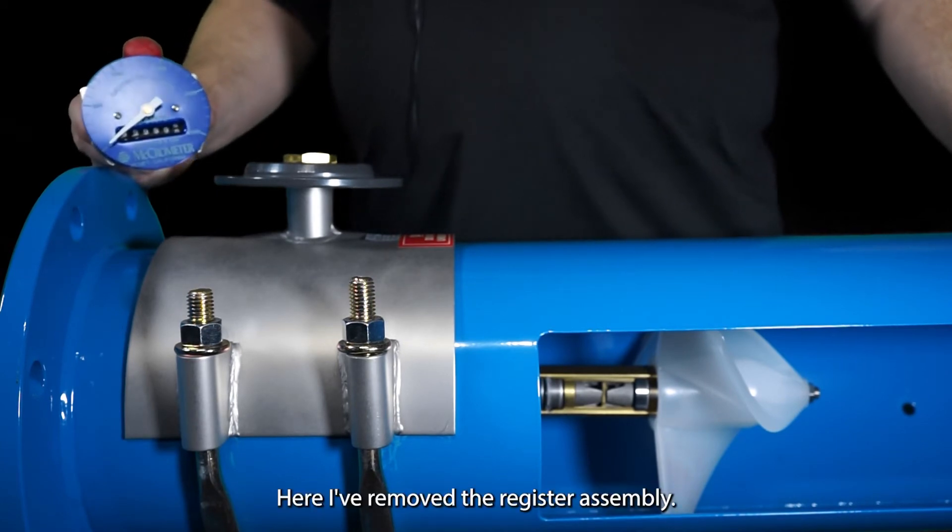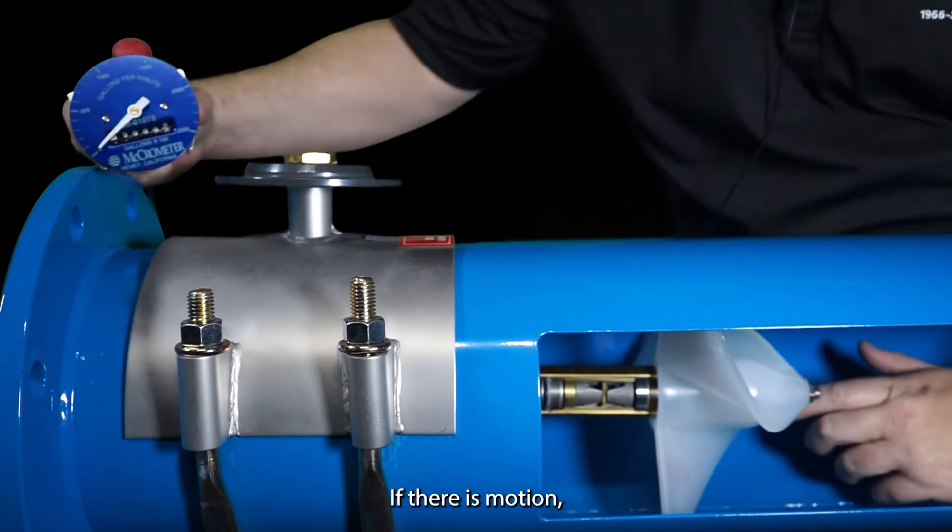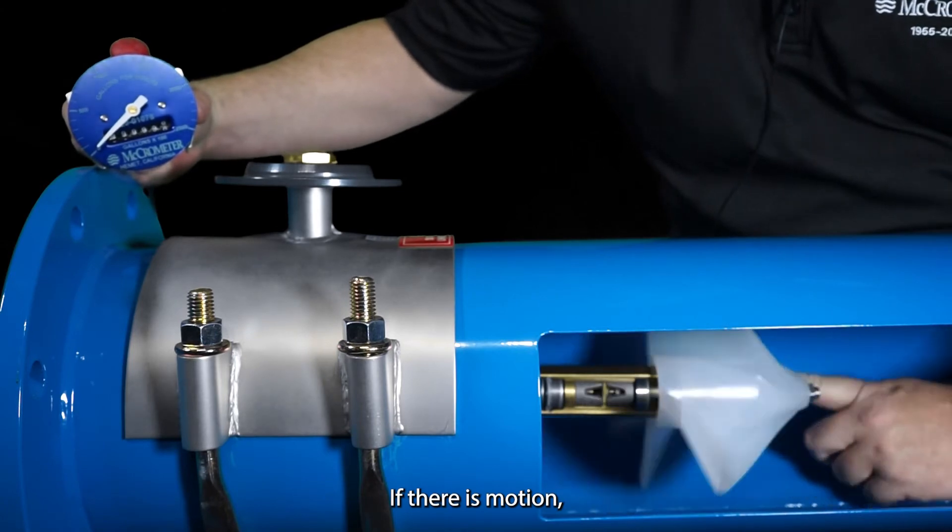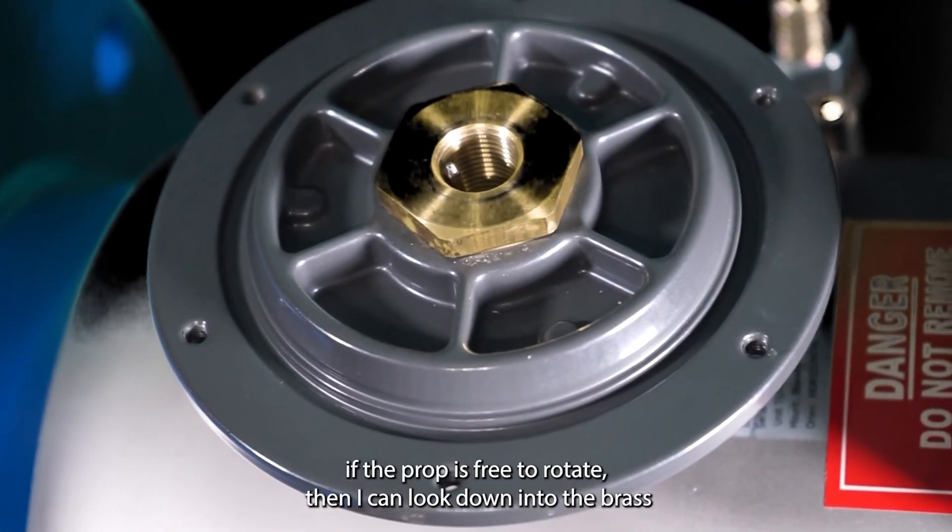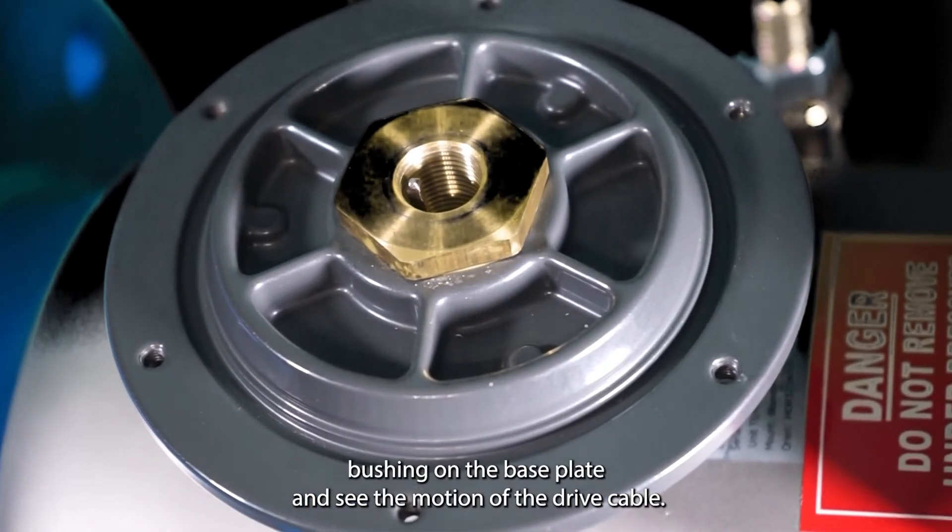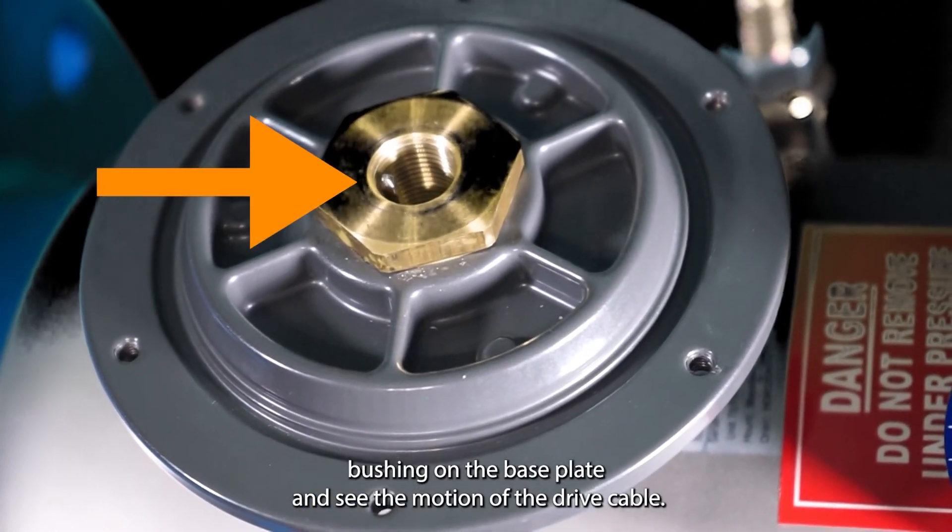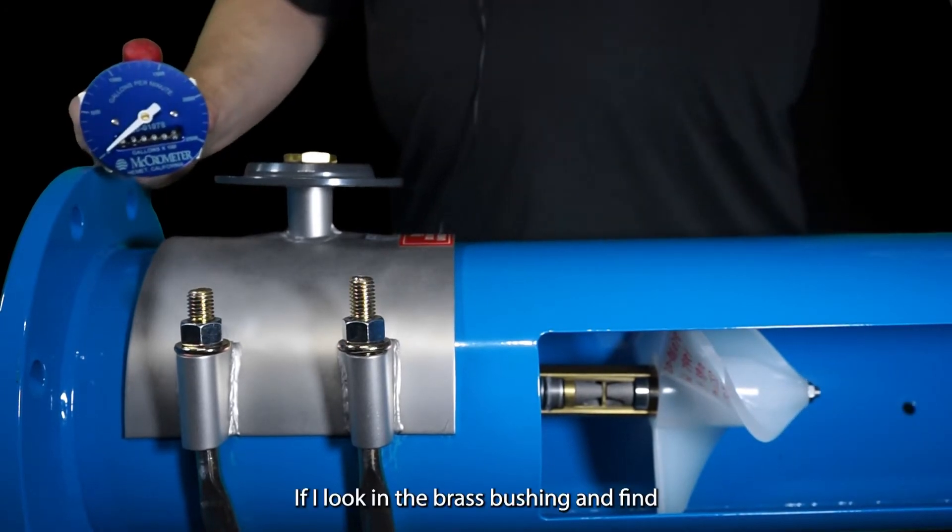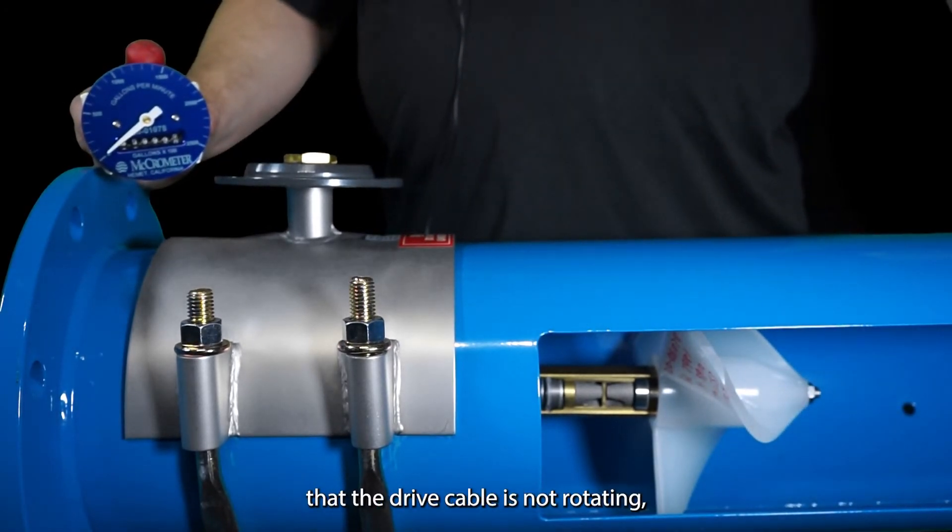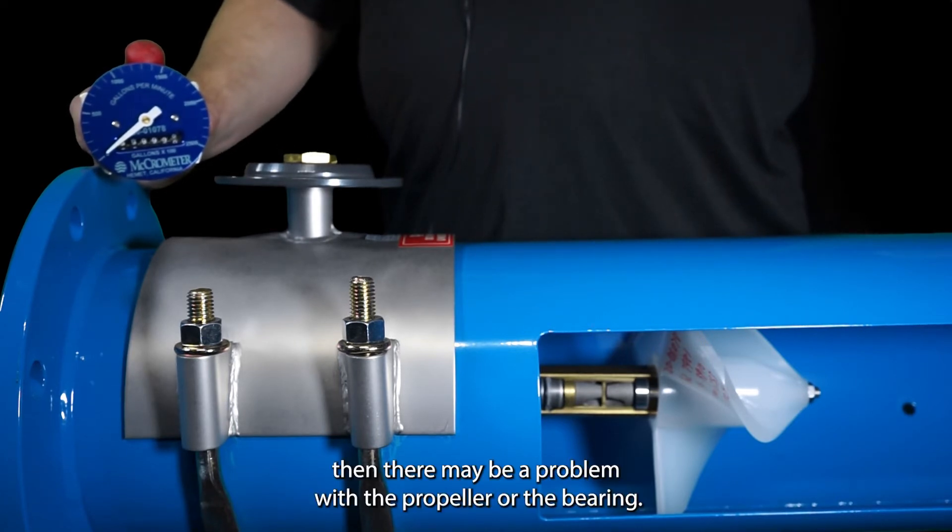Here I've removed the register assembly. If there is motion, if the prop is free to rotate, then I can look down into the brass bushing on the base plate and see the motion of the drive cable. If I look in the brass bushing and find that the drive cable is not rotating then there may be a problem with the propeller or the bearing.